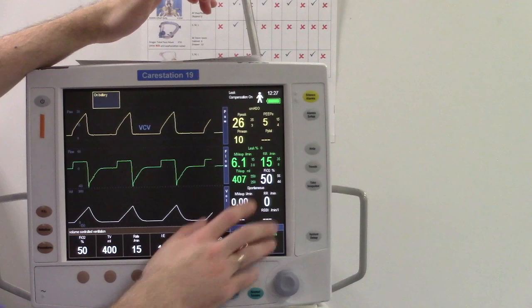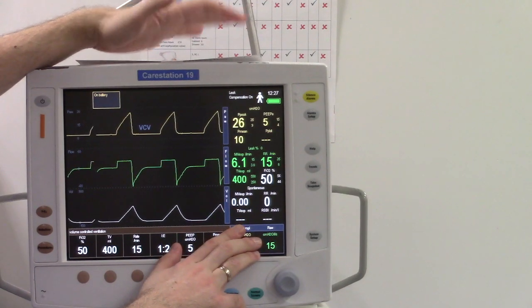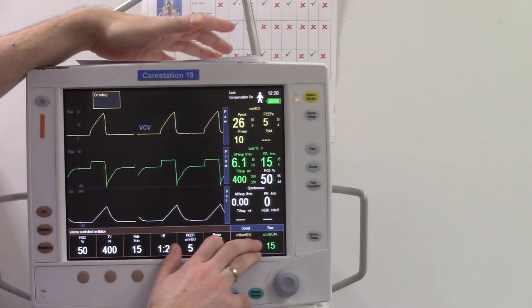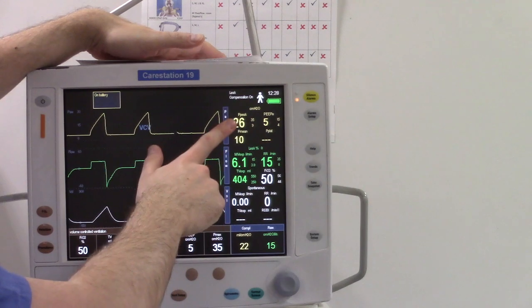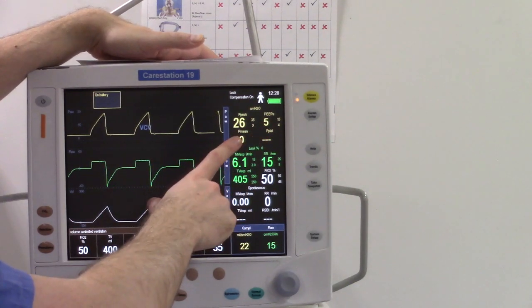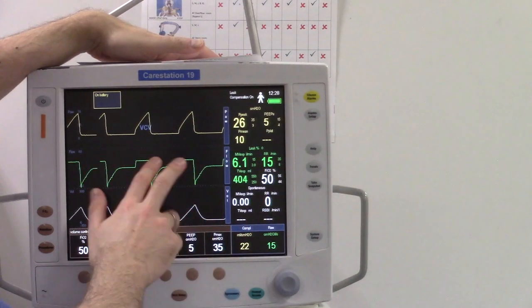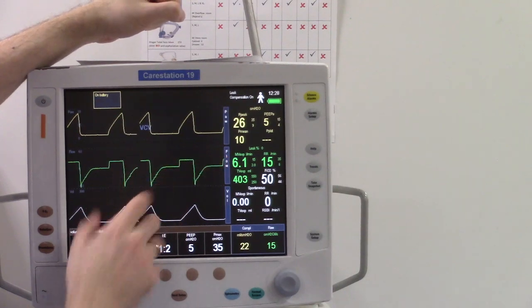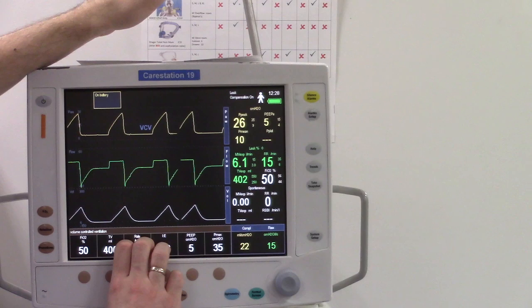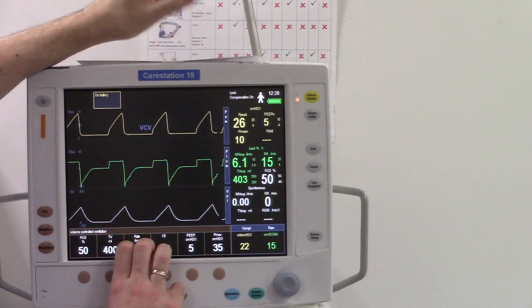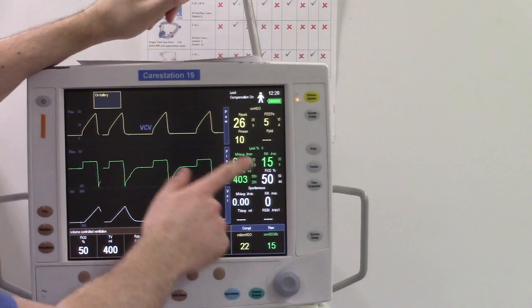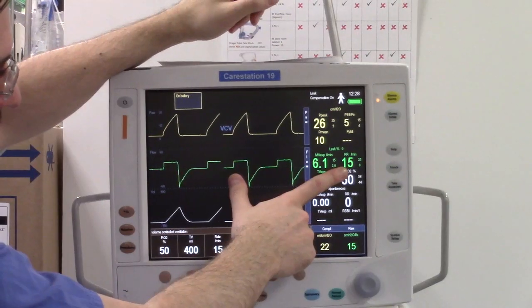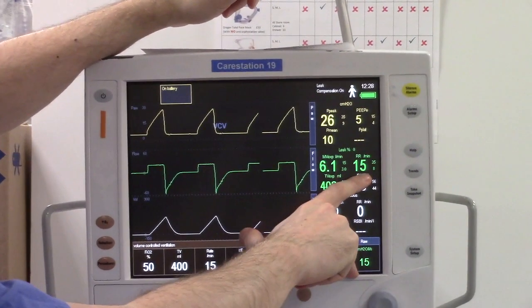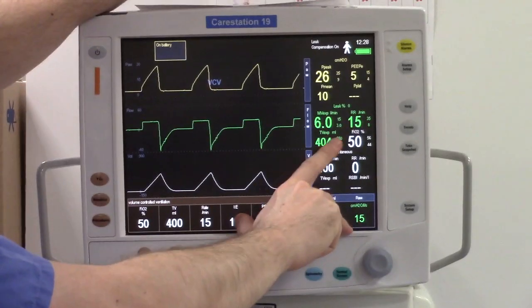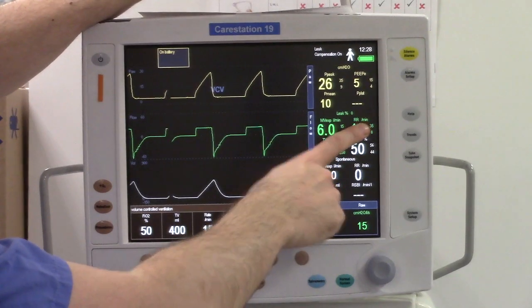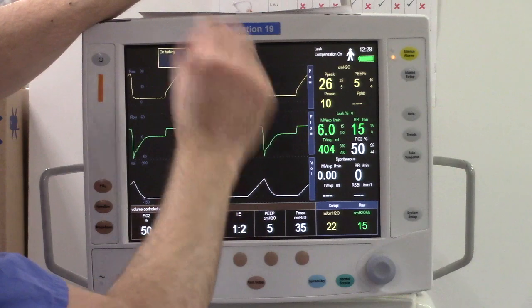On this side we have the digits that will actually show you the values of those specific parameters. Pressures, we have the peak pressure, we have the average or mean pressure. Then here the volumes, the flow, minute volume, which is the volume in 1 minute, or it's equal to tidal volume in one respiration times the number of respirations. So 6.1, 15 breaths per minute. If you think quickly about it, 400 times 15 is about 6,000 milliliters, which is 6 liters. So this times this should always be approximately equal to this.